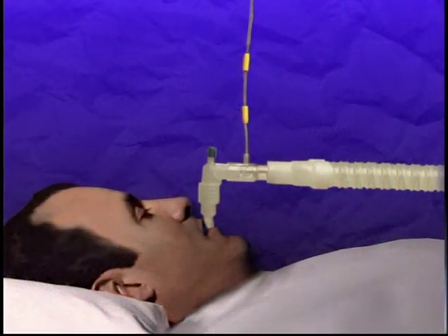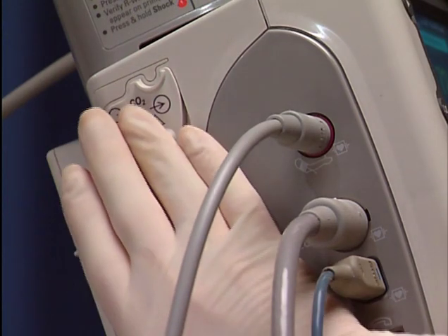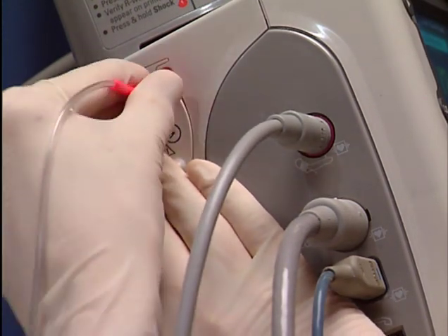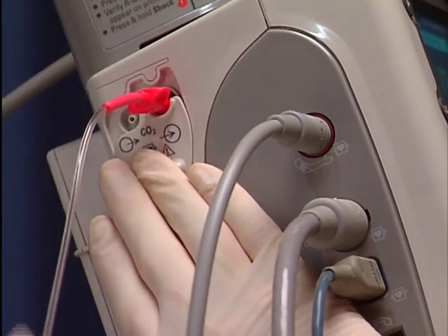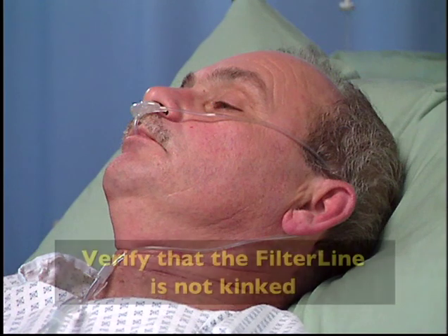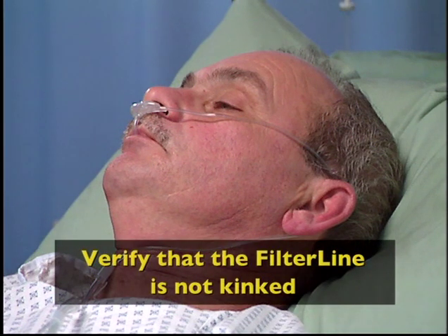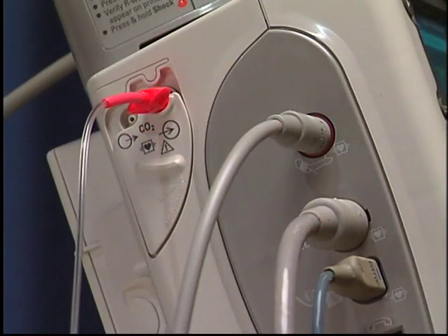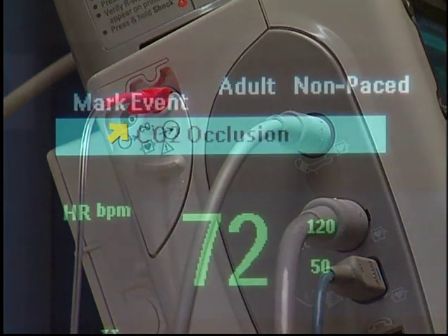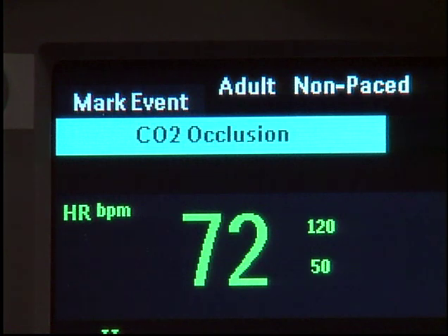When using a filter line set, place the pre-attached airway adapter on the ET tube. Attach the female luer connector of the nasal cannula or airway adapter to the CO2 inlet connector on the measurement connector module. Regardless of type, nasal or intubated, verify that the filter line is not kinked. To remove exhaust gases from the system, connect an exhaust tube or closed loop kit to the connector. Evaluate the filter line if a CO2 occlusion INOP appears or if the readings become extremely erratic.